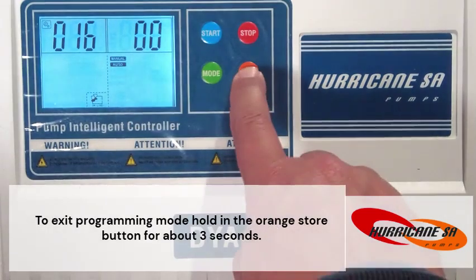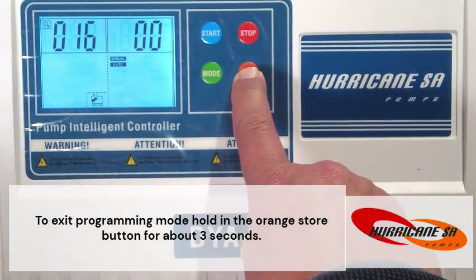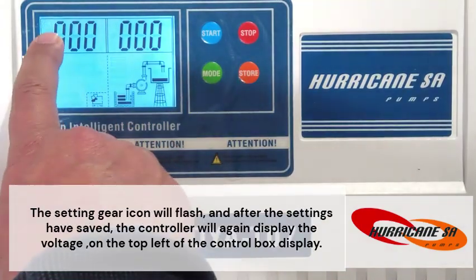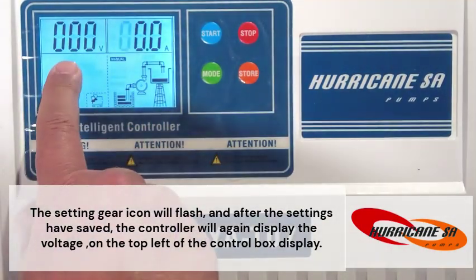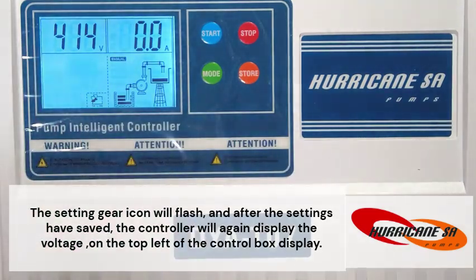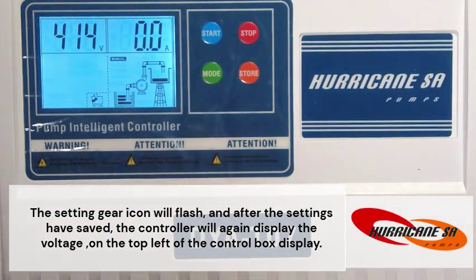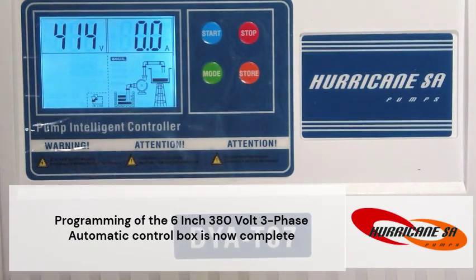To exit programming mode, hold the orange store button for about 3 seconds. The setting gear icon will flash, and after the settings have saved, the controller will again display the voltage on the top left of the control box display. Programming of the 6-inch 380-volt 3-phase automatic control box is now complete.